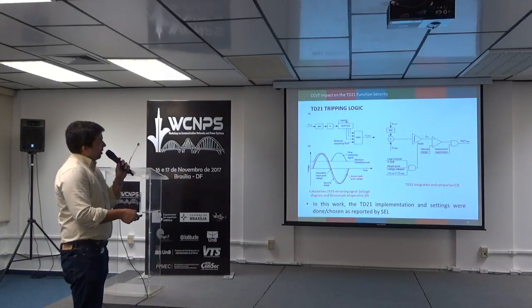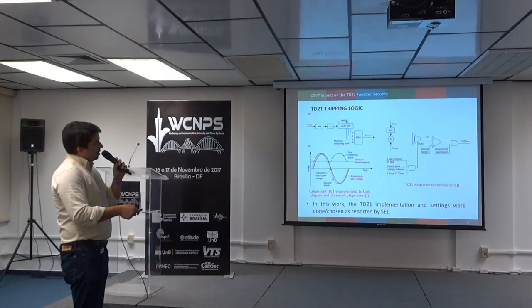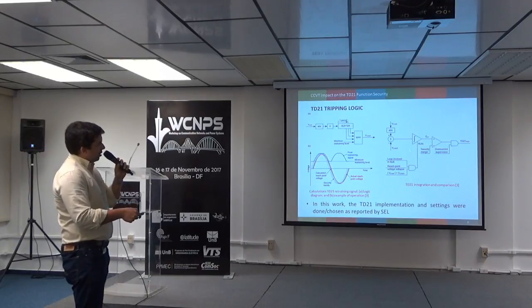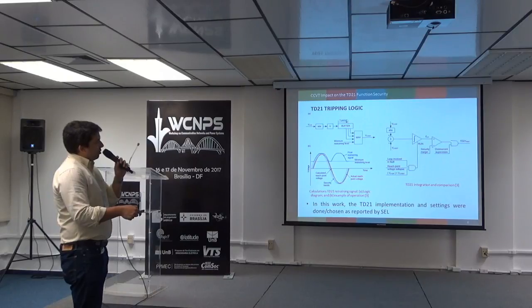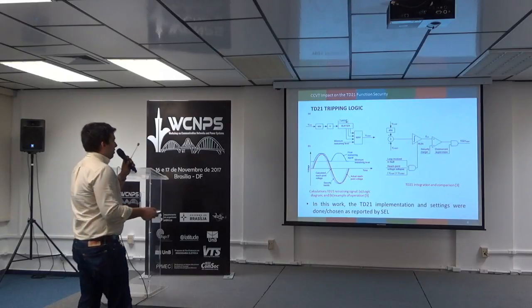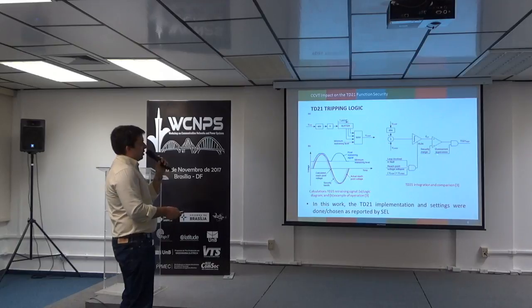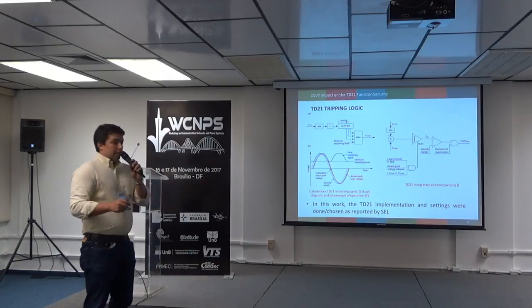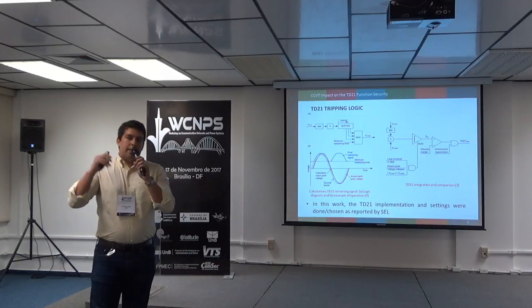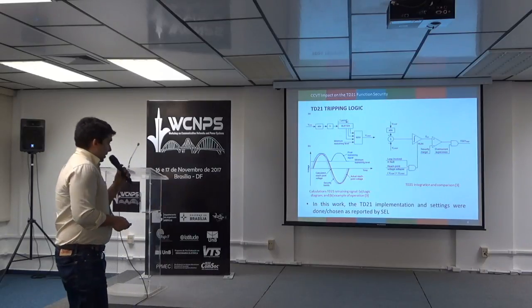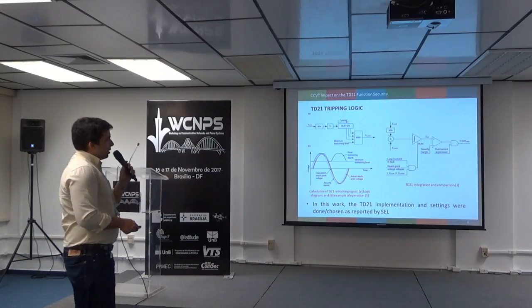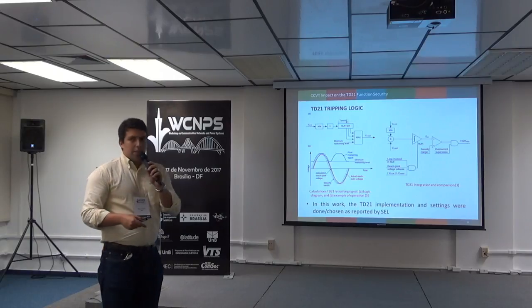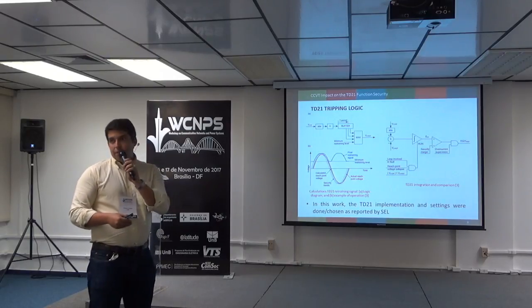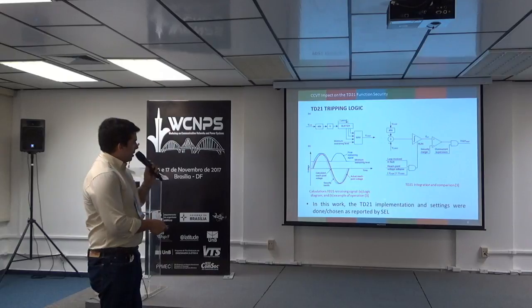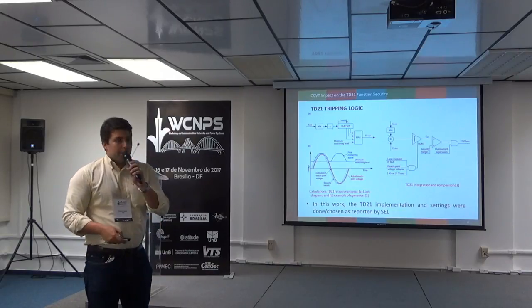are met, an integrator runs, integrating the signal, and if this integrated signal is greater than a security margin, we have the operation of this TD21, whenever the overcurrent supervision indicates that a fault current level is higher than a threshold. In this work, the TD21 was implemented and set as reported by the developers of this function, in this case, Schweitzer Engineering Laboratories.